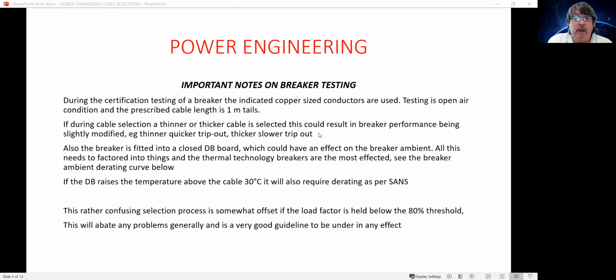And yeah, we've had feedback where people said, well, I've put 120% on the breaker and it never tripped out. Well, the breaker will never trip out. It's not designed to trip at that level. It's perfectly okay. The cable will get jolly hot, we understand, but it will not get catastrophically hot. Of course, ambient makes a difference. We are talking about cable at 30 degrees, and the moment we close the panel board up, 30 degrees is pretty hard to maintain in a running condition.